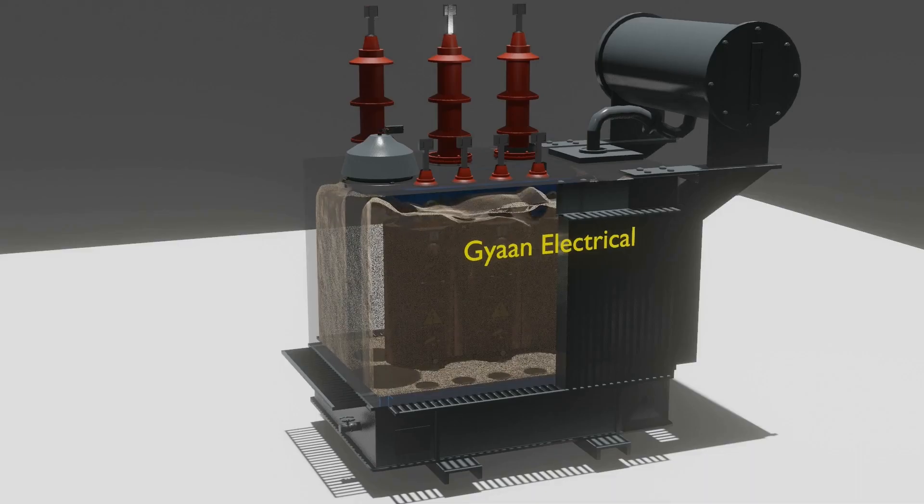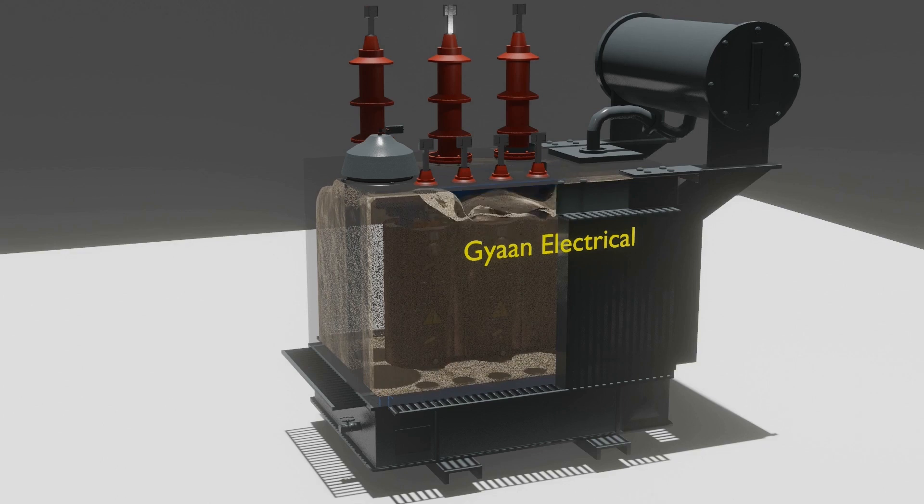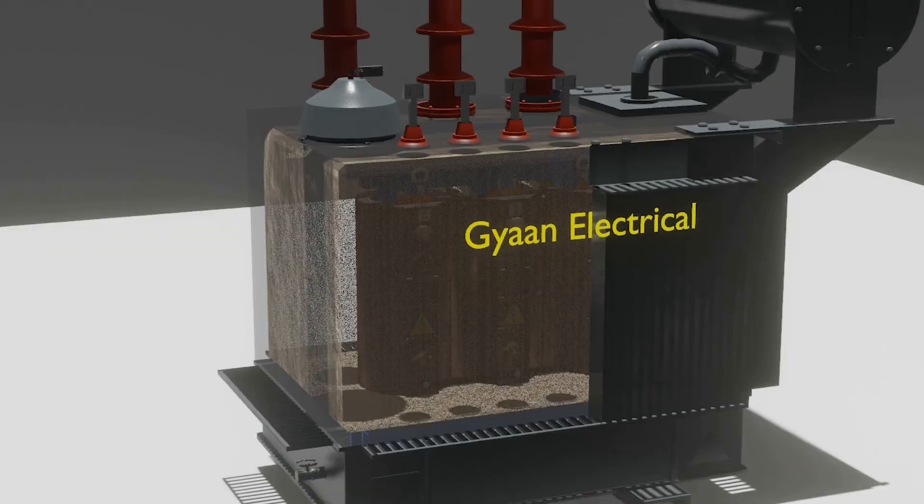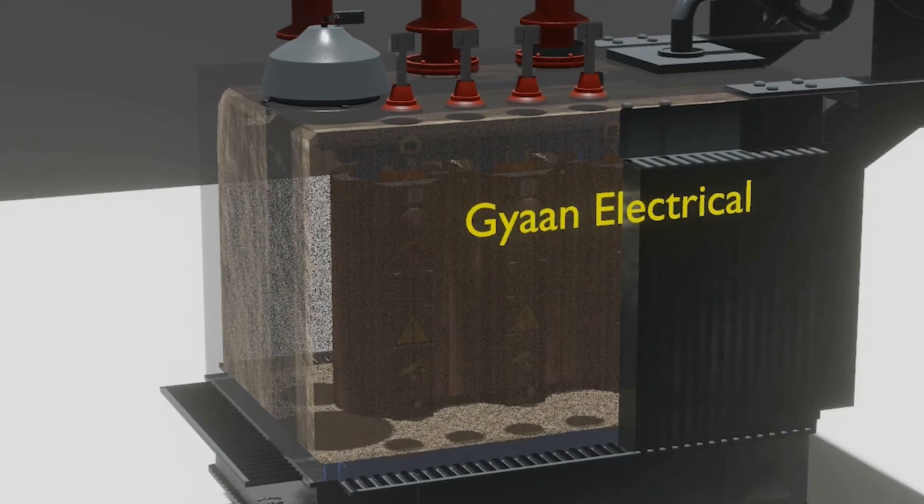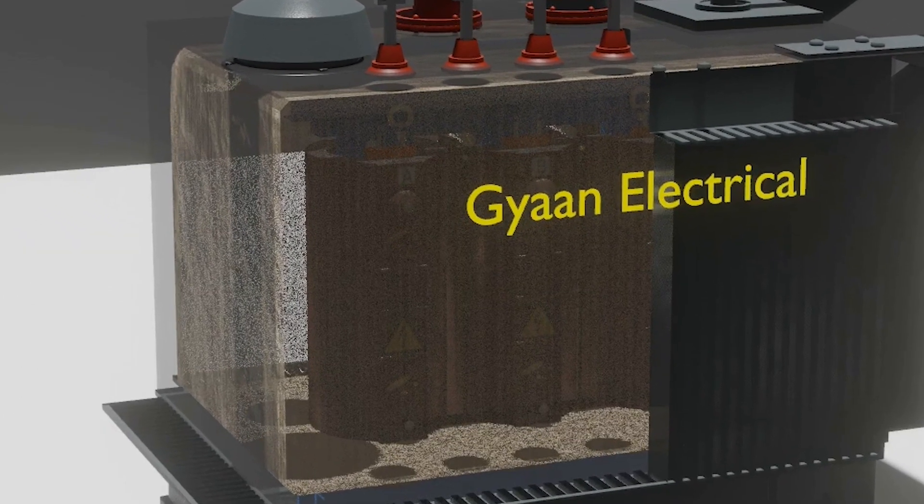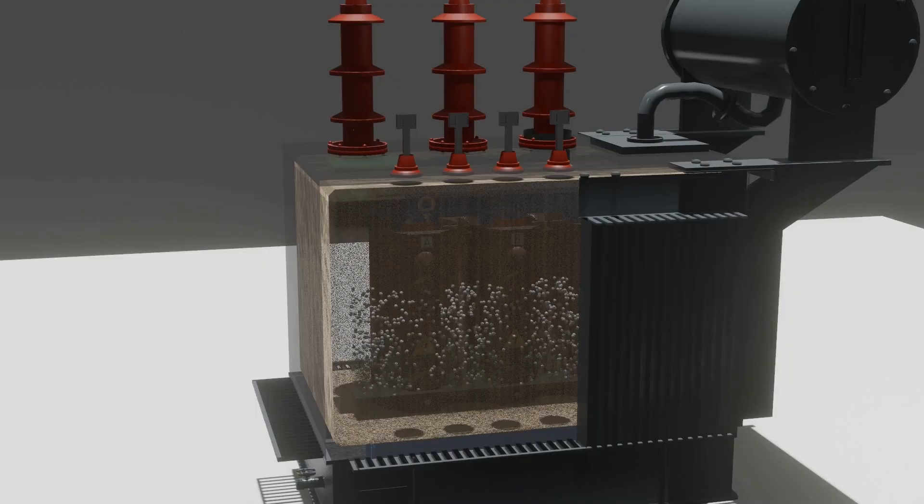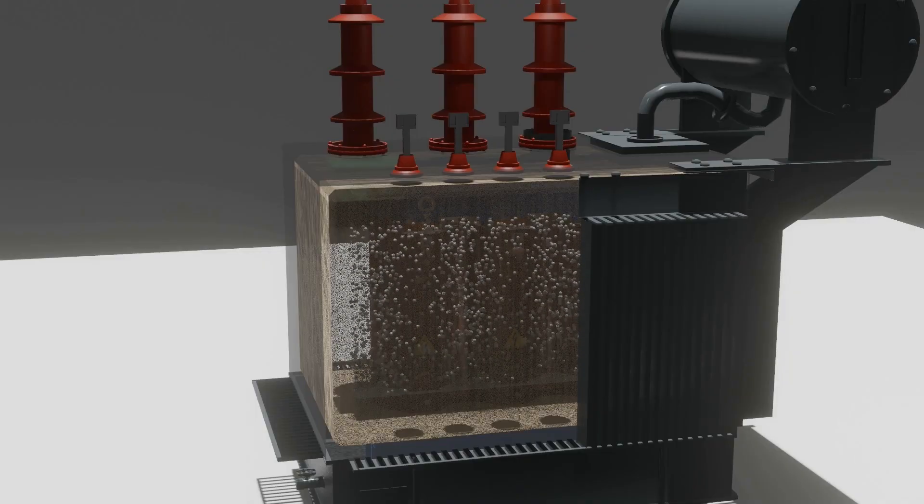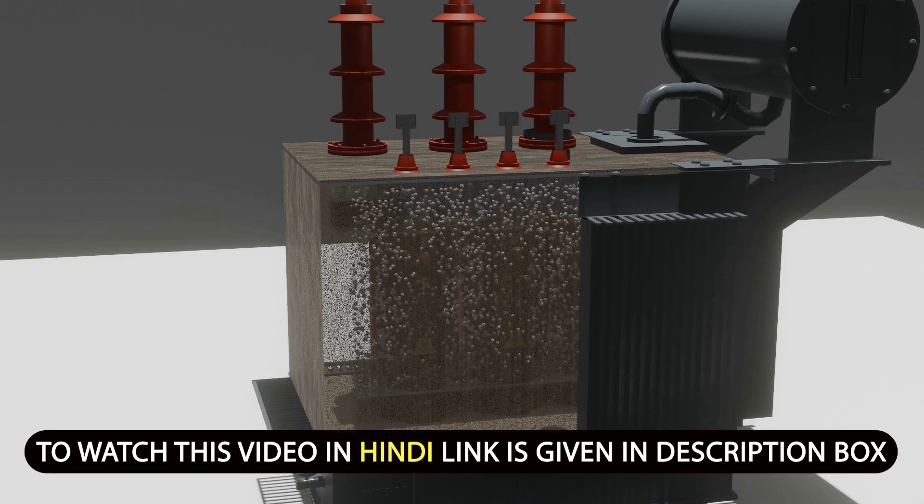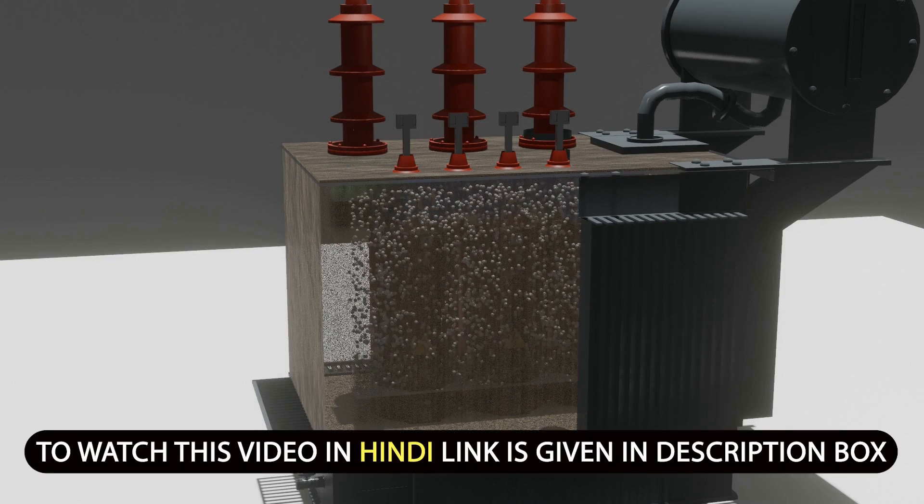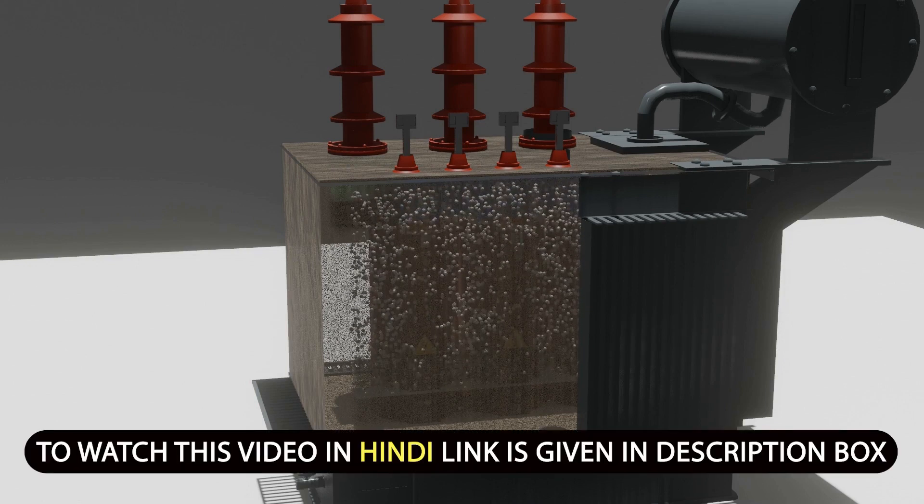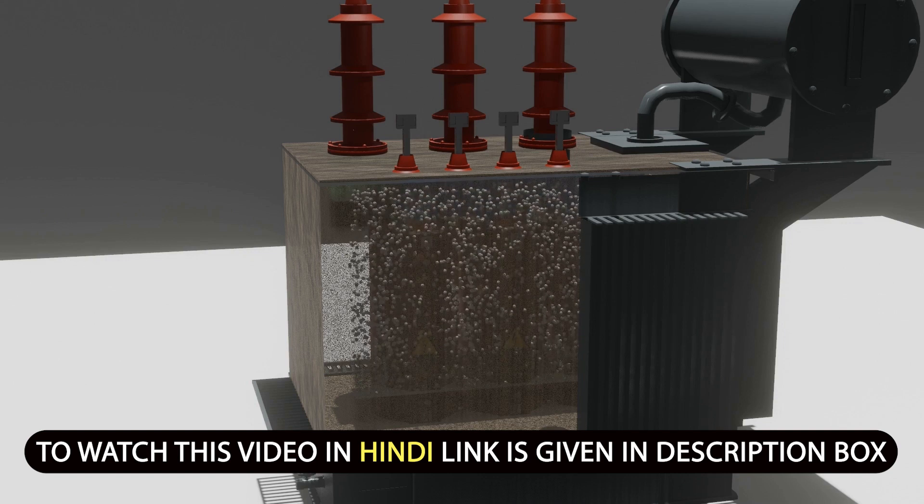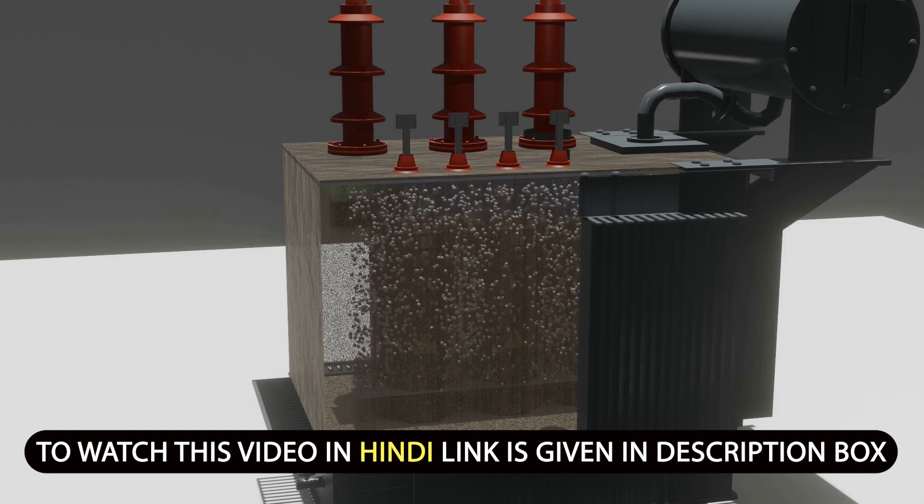As we all know, inside the transformer the insulation oil is used, and it used to provide insulation and cooling to the winding of the transformer. But if by chance the fault occurs in the winding and core, it will lead to the oxidation of insulation oil as you see here, and due to that it will produce a very high amount of gas inside the transformer tank. And if we have not used PRV in the transformer, then pressure build up inside the tank and tank will rupture.